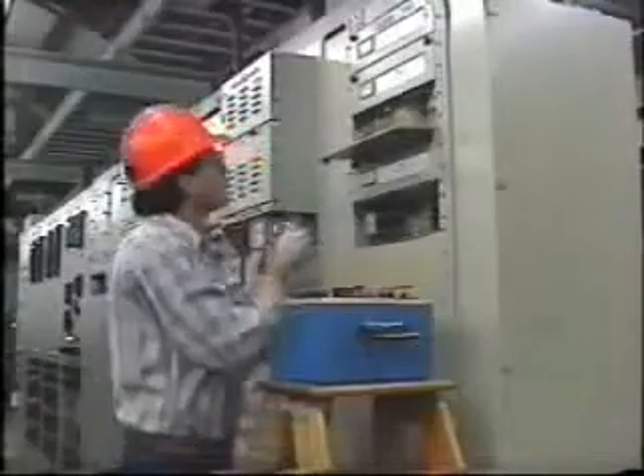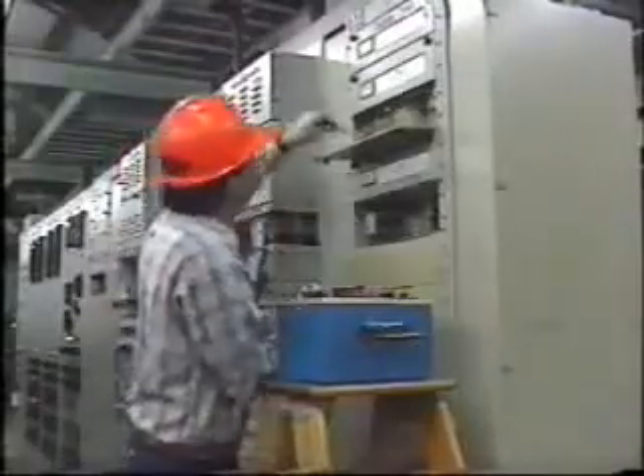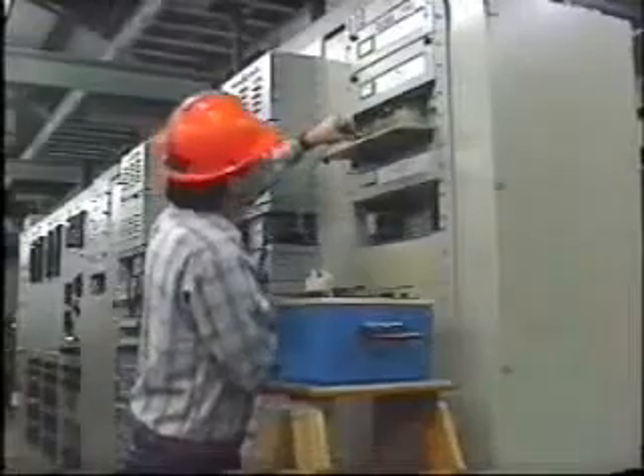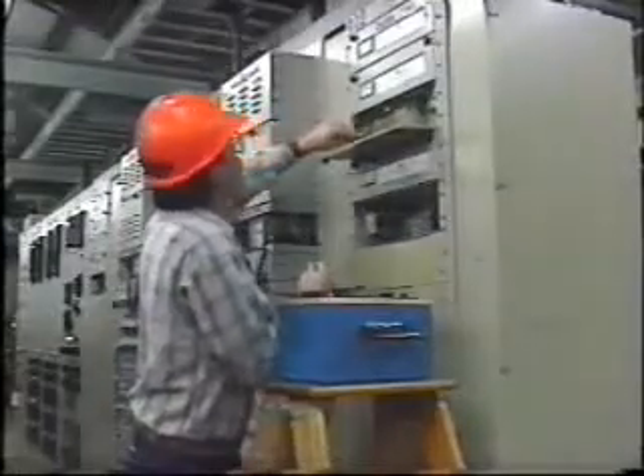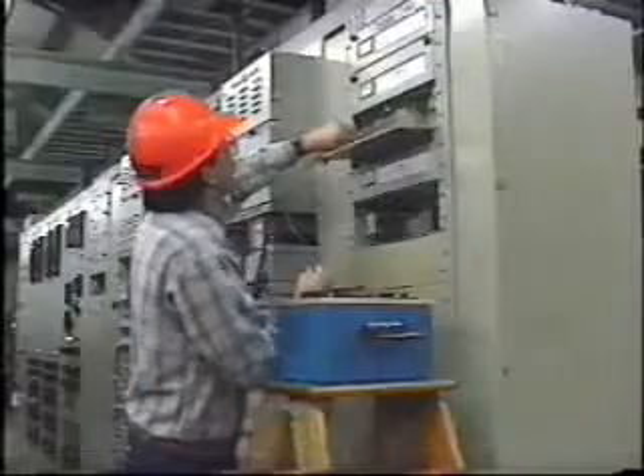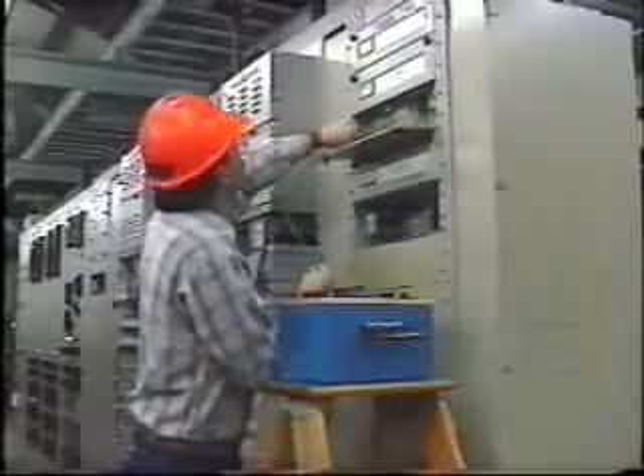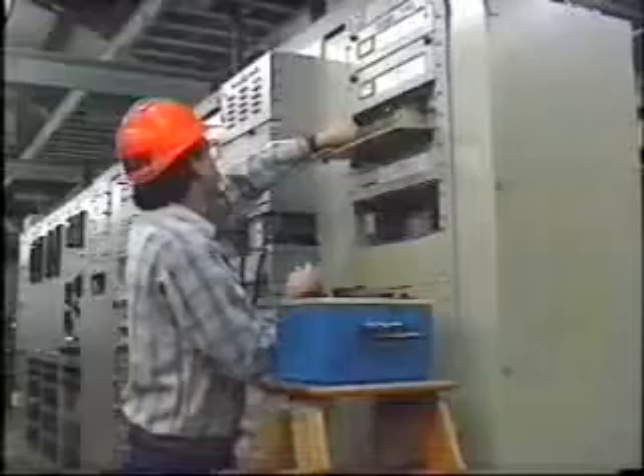Good housekeeping is extremely important while performing tests. Cables, wires, and tools spread around the work area are certainly conducive to accidents. All connecting leads should be kept neat and routed out of walkways. Remember that a relatively small accident, say tripping over a temporarily connected cable, may conceivably cause the victim to fall onto live terminals on a panel, possibly inflicting considerably more injury.